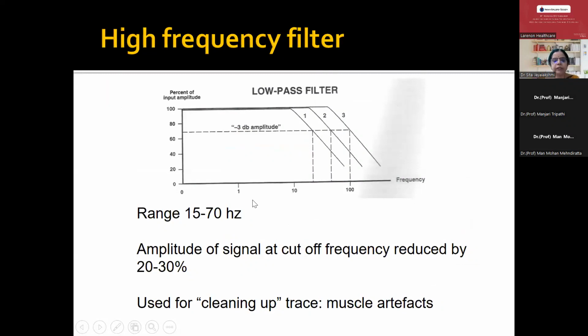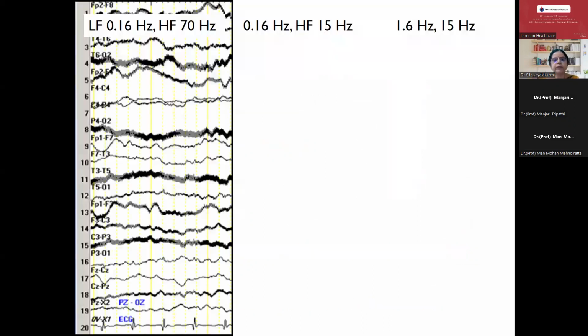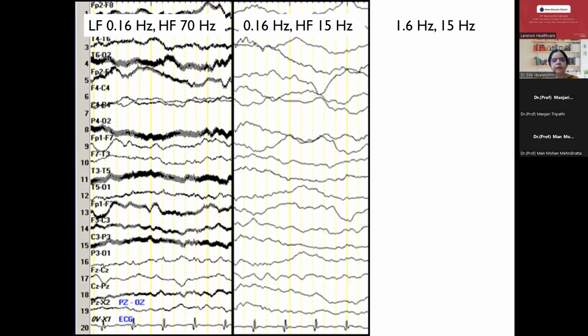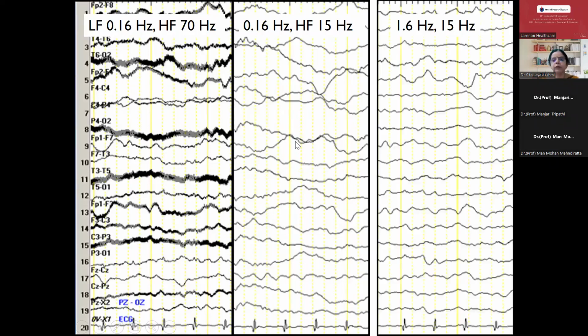Ideally, we should record at 70 hertz only, even if you are not getting a very smooth EEG. At the cutoff frequency, the amplitude of the signal is reduced by 20 to 30%. If you see, this is the recording at 70 hertz. This is not a good recording, so you need to really work on your placements, the impedance and the resistance. If you change to 15 hertz to have a good recording, which is what we most of the time get when we get the reference from outside, you see the EEG recording is so smooth, which is not at all good. We should never do that, and we should always record as far as possible at 70 hertz.